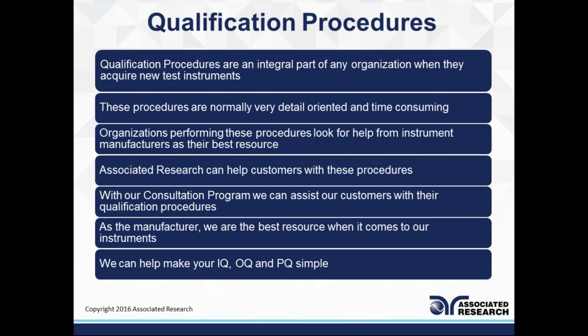Now, once you decide, you move into the installation qualification, where the instrument or equipment being qualified, as well as all its subsystems, because test setups and systems can contain multiple testing equipment, as well as its subsystems and any ancillary systems, have been delivered, installed, and configured in accordance with the manufacturer's specifications or installation checklists. Again, this is where we come in. As a manufacturer, we will have all that information for you, and we would be your best resource.